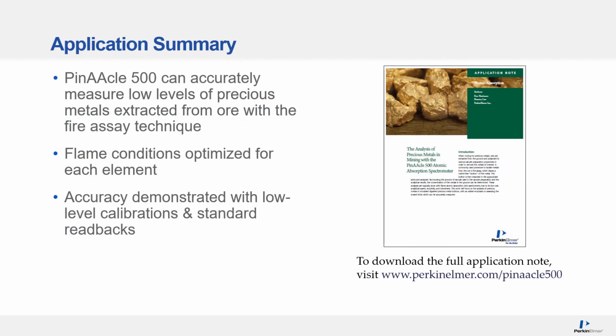So in summary of this application, I hope that we demonstrated that the PinAAcle 500 AA is usable for accurate low measurements of precious metals. It also demonstrated the ability to optimize the flame conditions for each element individually. And we also showed the accuracy with low-level calibrations and standard readbacks.